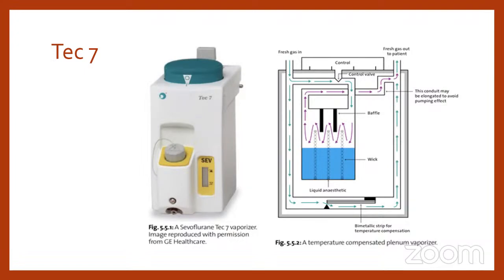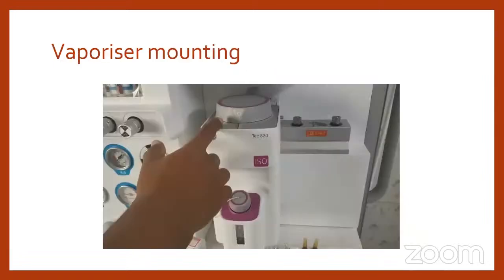Otherwise, when we tilt or invert the vaporizer, the liquid present in the reservoir will come out of the system and cause accidental inhalation by the providers. So to avoid this hazard, we have incorporated another safety mechanism to maintain the liquid level even if we invert or tilt the vaporizer. And this is the vaporizer mounting unit. It has 2 pins and a locking system at the center. Whenever we use these kinds of vaporizers, they will be mounted on this. Most of our systems have 2 mounting units, so we can mount 2 vaporizers, but we can use only one vaporizer at a time.